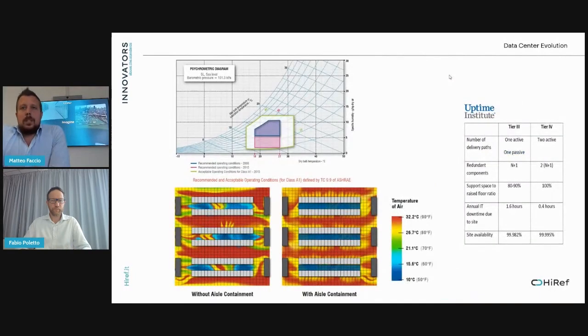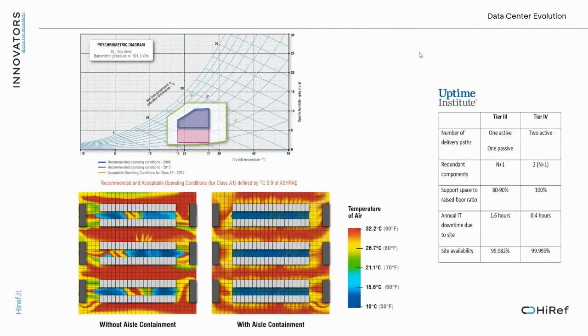What can we do? Basically, we can work on 3 main arguments. First of all, we need to take care of the operating conditions inside the white space. ASHRAE indicates this, so it's really important to follow the recommended operating area and, where possible, also look at the acceptable operating conditions. Secondly, we need to make use of a containment system mandatory for the organization of the room. This simple CFD analysis clearly shows what is happening without the containment system and with the containment system.